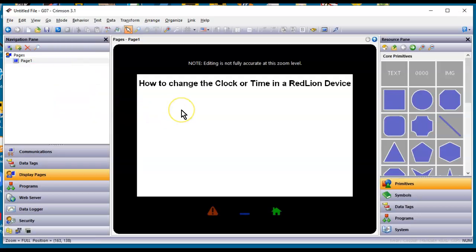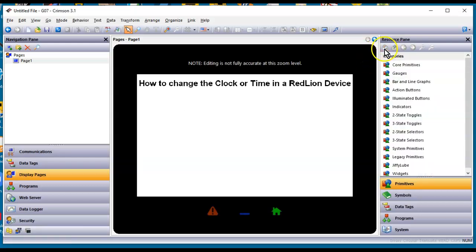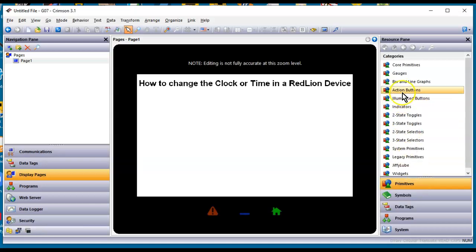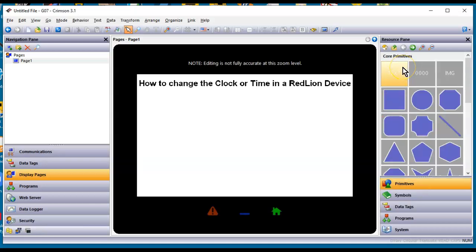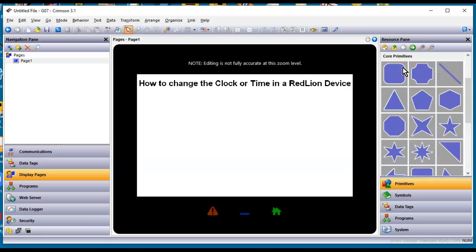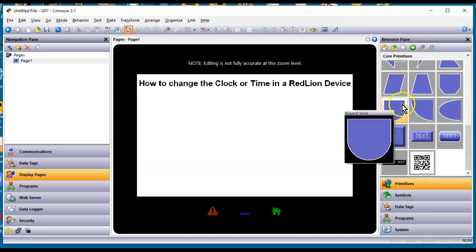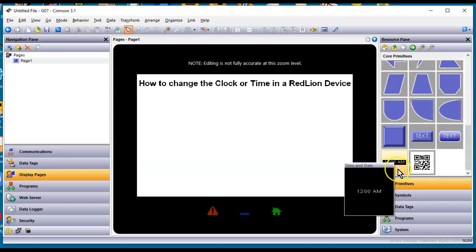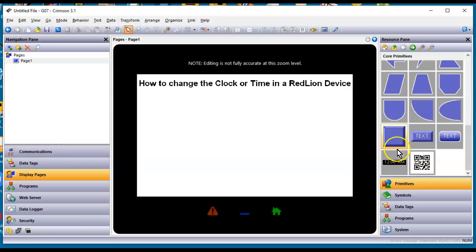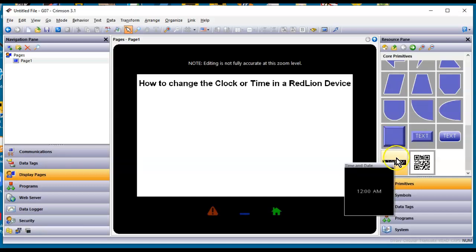Number two method you could contemplate is you could actually go over to the right side. If you're in Crimson, if you've got the database open of whatever it's running on, you can go to Primitives on the right side, go into Core Primitives. And in here, if you have a time primitive already on your screen, great. If not, if you slide all the way down to the bottom, in the lower left-hand corner, there is a time and date primitive.